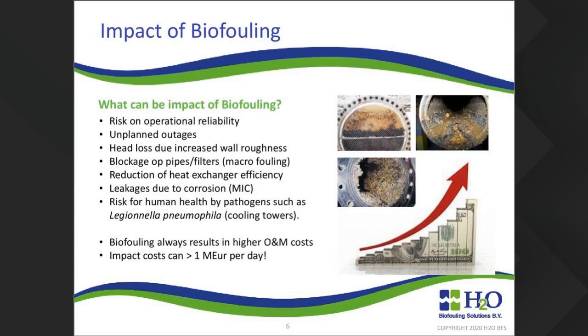Biofouling can result in operational risks on the operational reliability. It can cause head loss. So if you have shell growth in an intake pipe, it increases the wall roughness of the intake pipe, which will result in head loss in the intake basin where the cooling water pumps are located. Head loss can arrive pretty fast, even when you have a small layer of fouling of mussel organisms settling in the pipe. So visually it doesn't look bad, but it already can have a very significant impact on head loss, which can trip a plant due to the low levels of water.